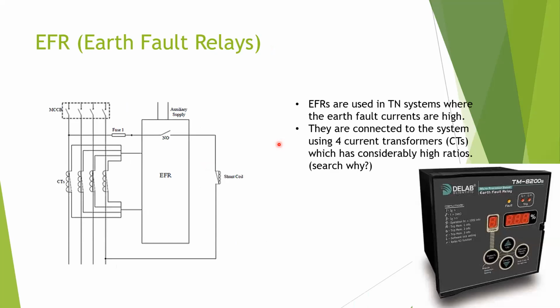And the next one is EFR. EFRs are used in TN systems because TN systems have high fault currents. So usually those fault currents cannot be measured by a small device. What we do is use a current transformer to take a ratio, because these usually come in high ratios. So 100 amps through this line will induce 1 amp through this loop. So CTs work in that way.